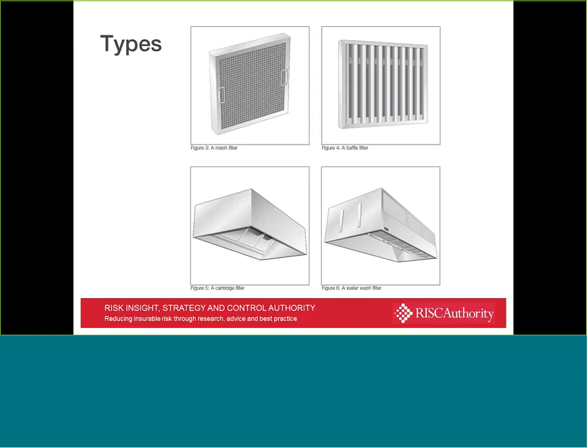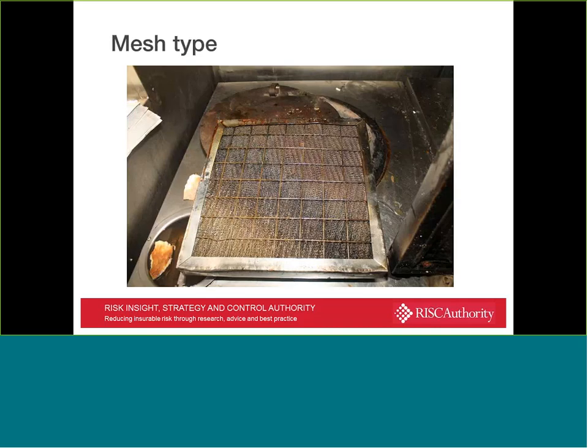There are a number of different types of filters: mesh type filters, baffle filters, an example of a cartridge, and a water wash filter. And certainly in terms of the order in which I've described them, they go from the most risk from a fire perspective to the least risk from a fire perspective. The mesh types are a metal frame, steel frame, with a series of layers of mesh inside.